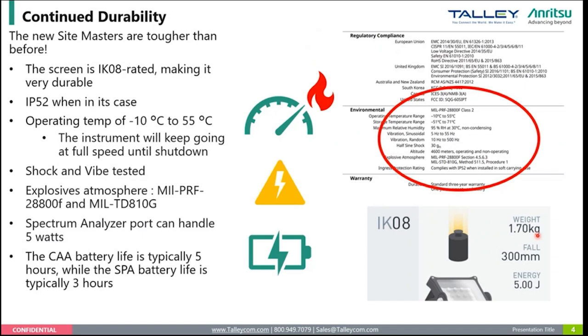And it's IP52 rated in the case. In other words, it can survive some moderate water environment, whatever the field throws at you. More than likely, the human factor is going to be the limiting factor, not necessarily the instrument. We've tested it, just like all instruments, environmentally. It can go from -10 to 55 operational. And unlike a lot of systems out there, when we say it goes up to 55, it goes up to 55 at full speed. There's no throttling. The instrument keeps functioning until it gets too hot and its self-shutdown capabilities kick in.